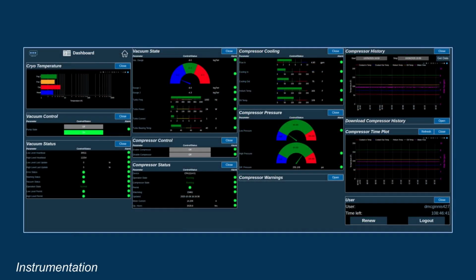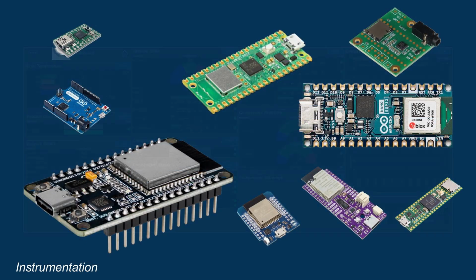Now we will take a look at the instrumentation needed for the test stand. Most accelerator instrumentation deals with rather mundane but extremely important functions such as measuring temperature, monitoring cooling flow, scanning vacuum pressure, and a host of other long-time scale or slow processes that protect and ensure that the system is operating within normal conditions. Since the mid-2010s, there has been an explosion of low-cost, high-performance microcontrollers.